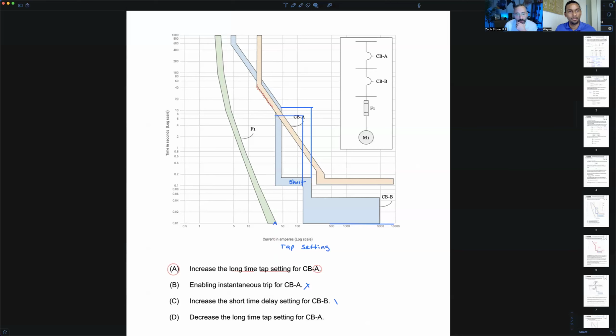I'm not sure if we could increase the short time that high, because now we're way into the time delay of long time. I'm not even sure if that would potentially be an option. We would only be able to increase it so much to still be within the short time region. But assuming we could raise it to the max, there's still going to be some overlap.